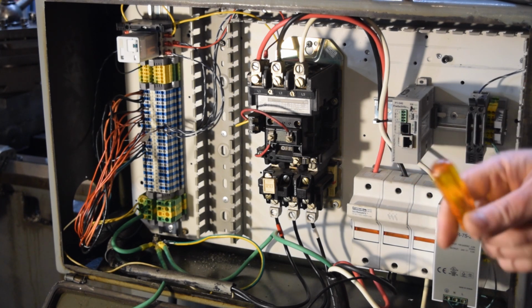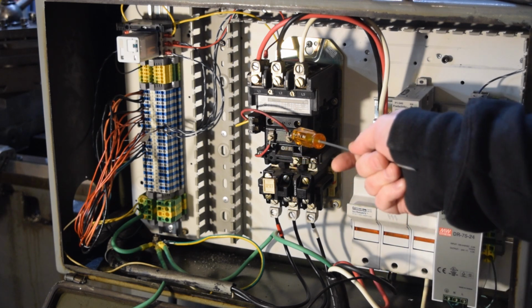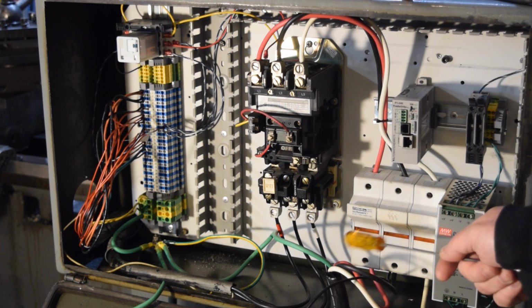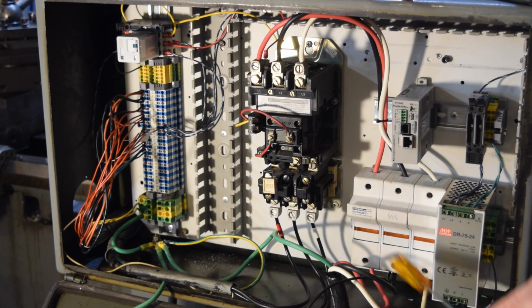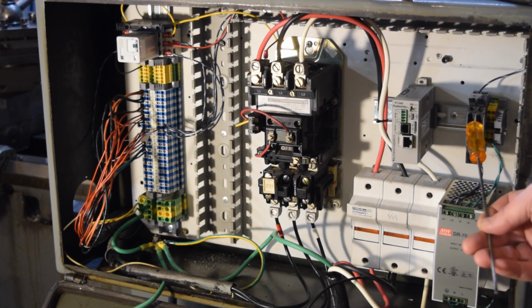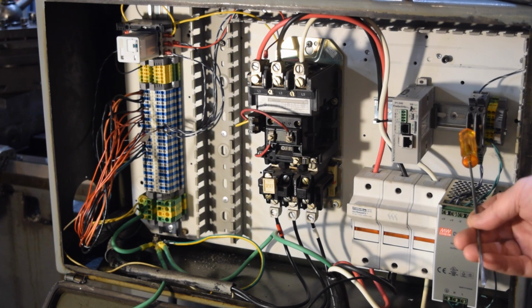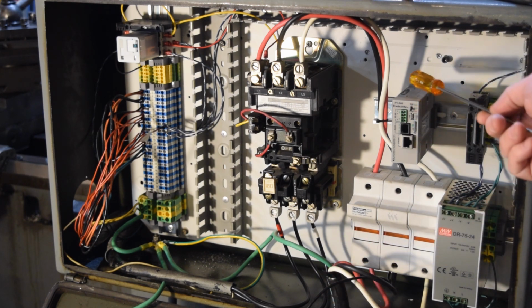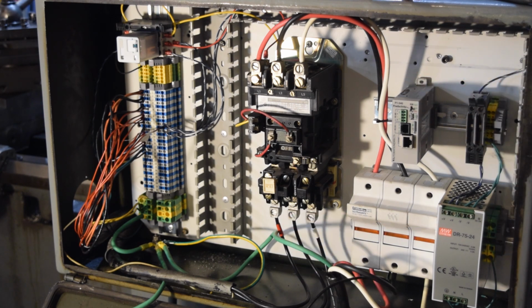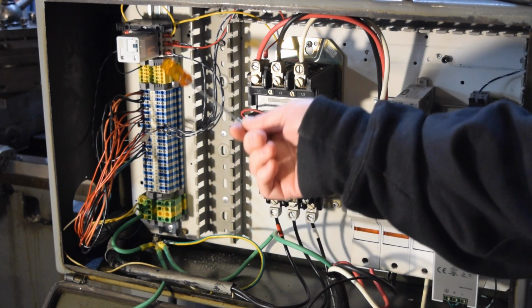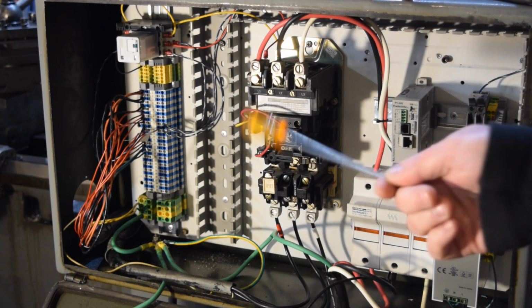I left the contactor installed in the original location here. Added the J-style fuse, added a 24 volt DC power supply for control voltage. Got a couple of fuse blocks here to fuse the 24 volt supply. This is the PLC that we'll be using in future videos. For reference, it's an Automation Direct Productivity 1000. Added Panduit all the way around.